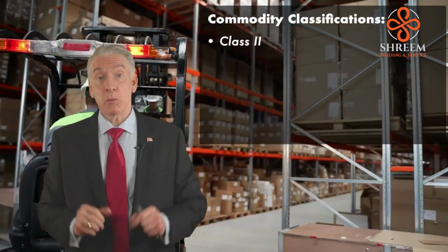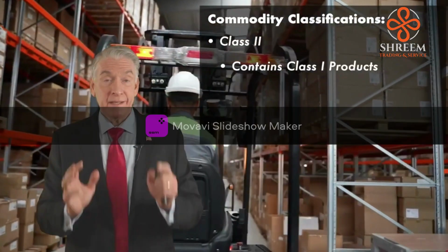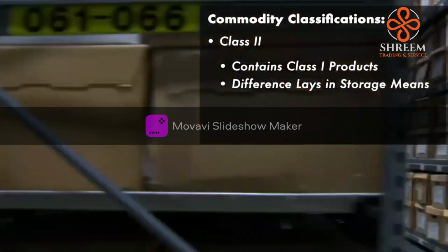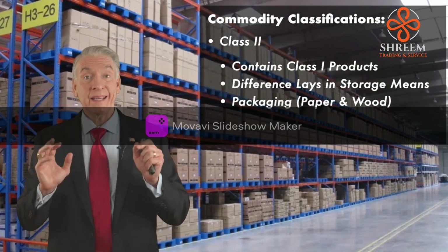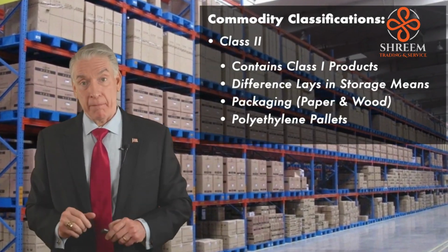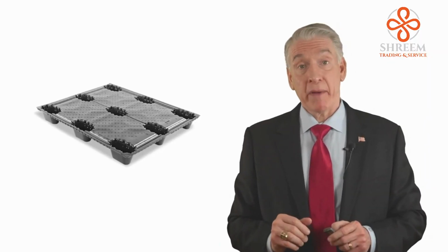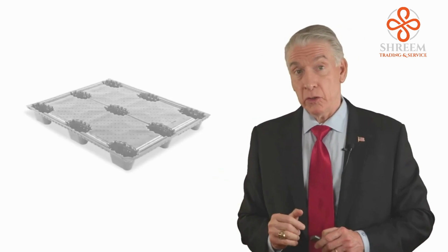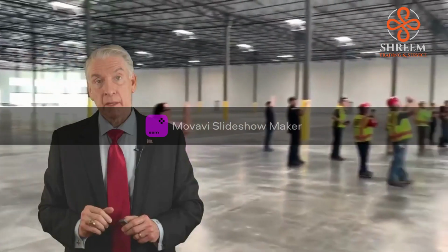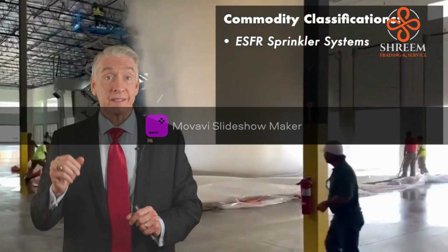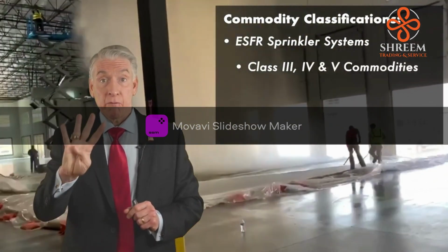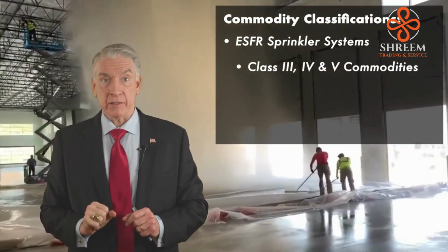Class 2 commodities are the same as Class 1 products, but the difference lies in how they're stored — are they stored in paper-type storage, or on polyethylene pallets? That raises them to Class 2, but wet sprinkler systems may still be sufficient. Then you get into ESFR sprinkler systems for Class 3, 4, and 5 commodities.